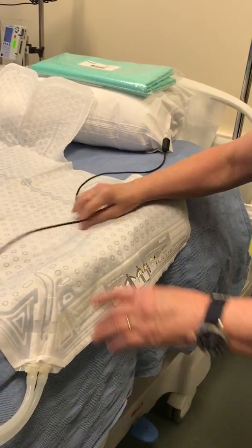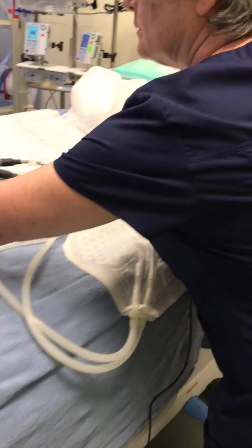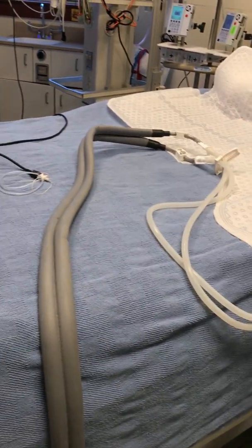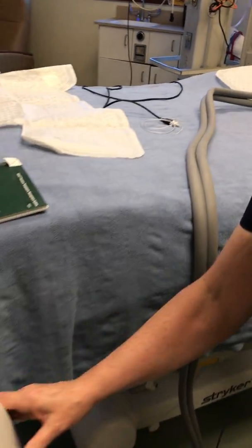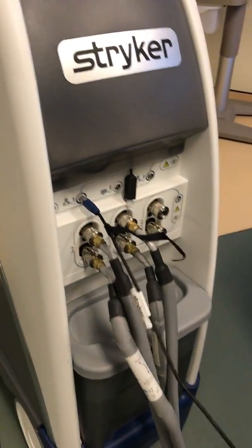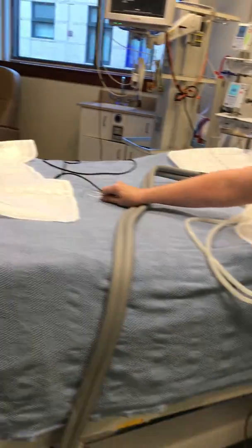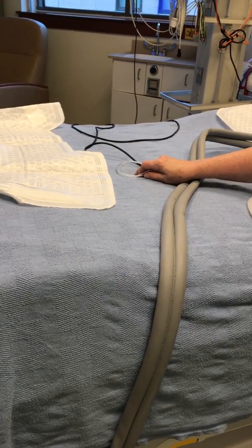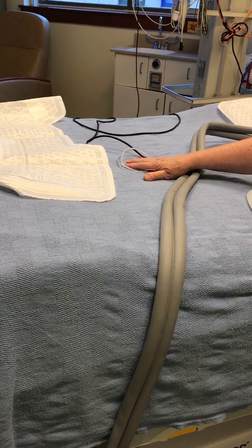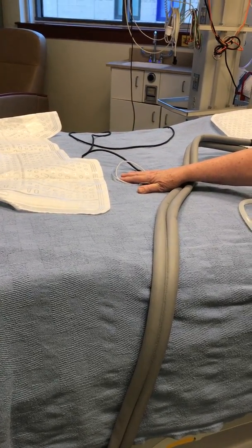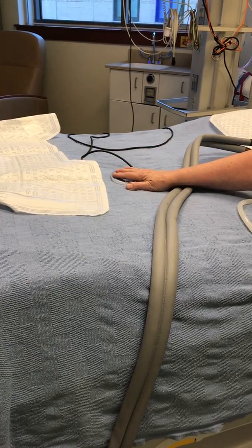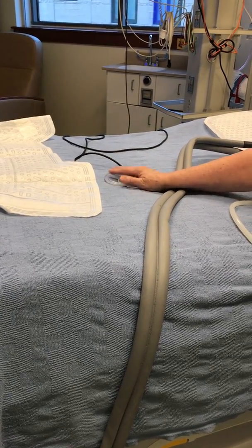esophageal, and then your secondary, which would be the primary, is attached to the machine back here, right here. And so it is set up to go into the esophagus, and then you always have a secondary to keep as a backup temperature to make sure you're running okay since you're doing therapeutic hypothermia. This will be either in the Foley or a rectal probe.